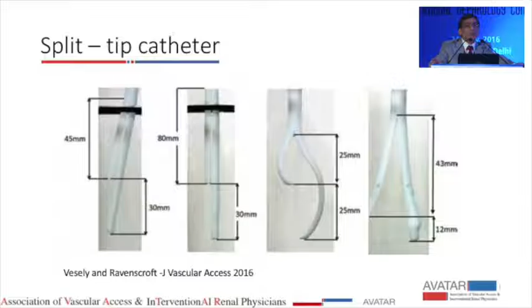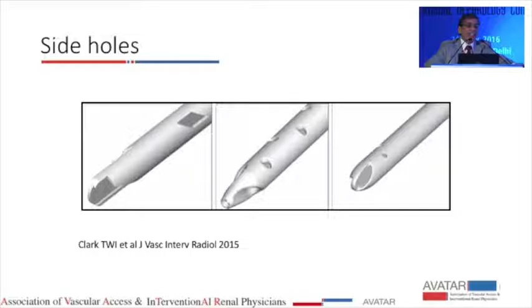If we talk about specifics, on the step tip catheter the distance between the arterial end and the venous end of the catheter can vary depending on what kind of catheter is being used. Similarly, in a split tip catheter, the length of the split, the distance between the splits, and the shape between the two split ends can be different. Some catheters also have flow dividers. So there are a lot of differences in the tips on the various kinds of catheters available in the market, making it difficult to identify and use a catheter that has the best performance, which is the ultimate goal.